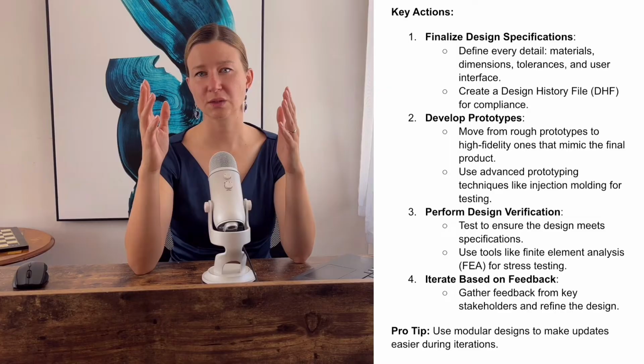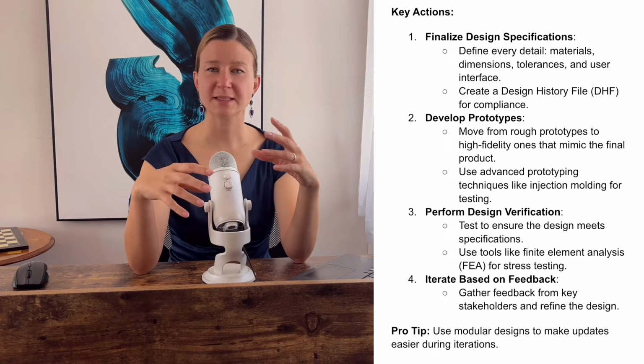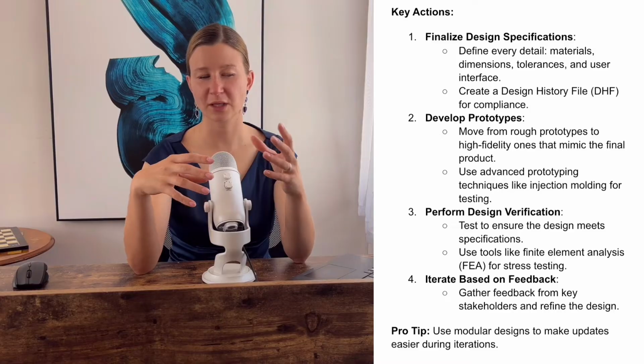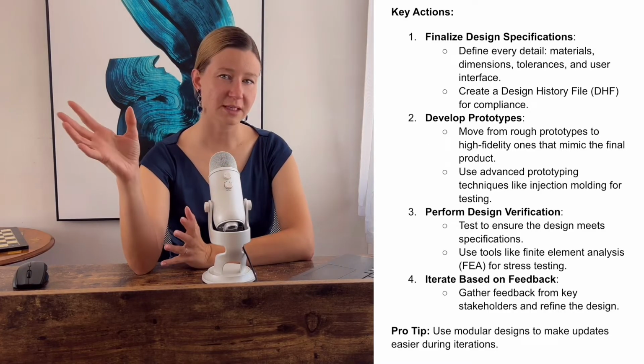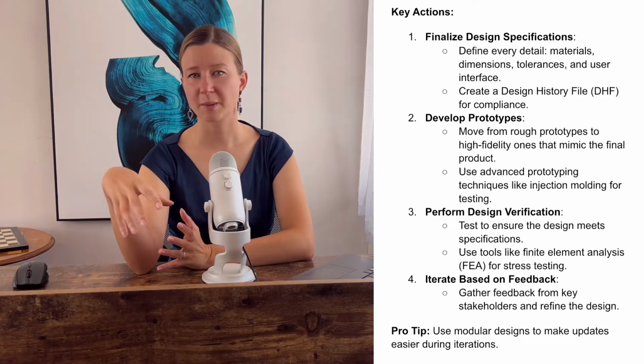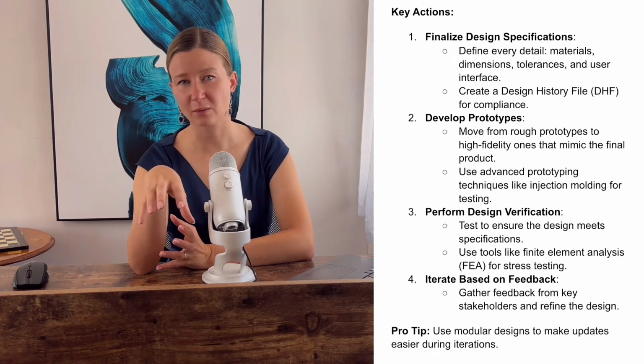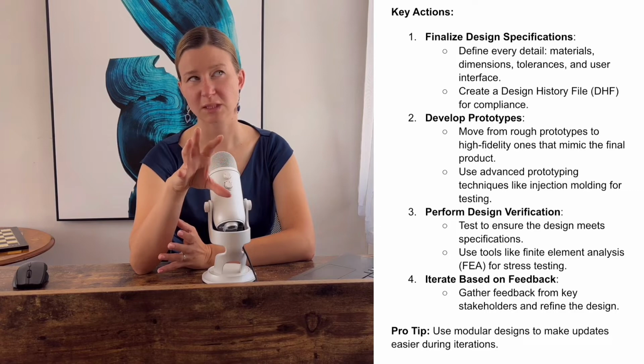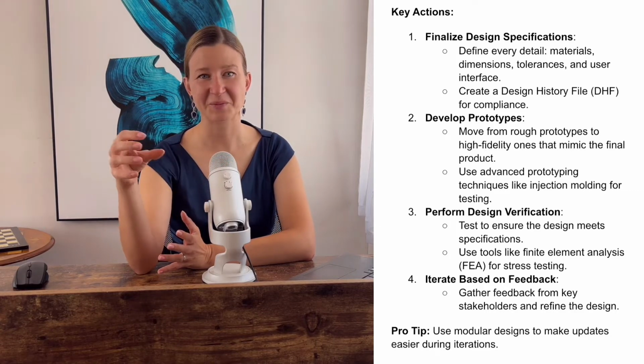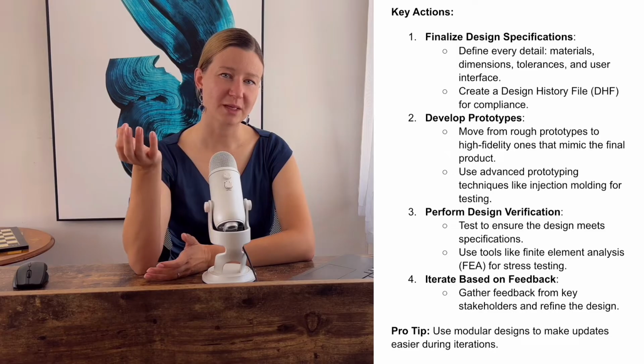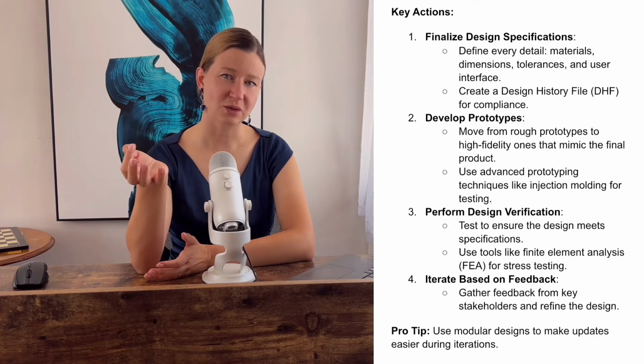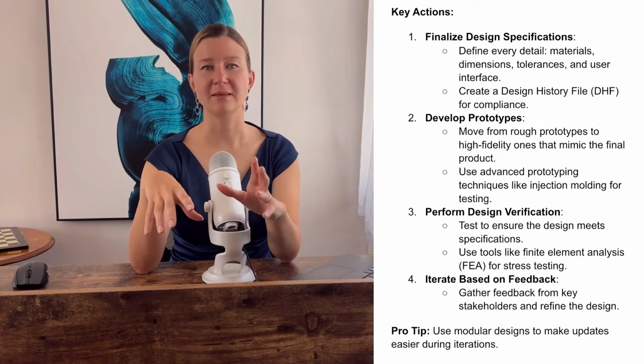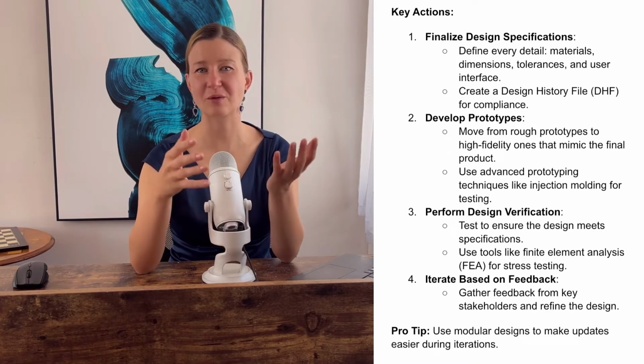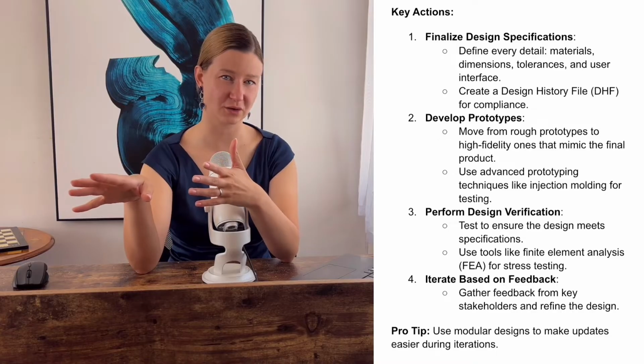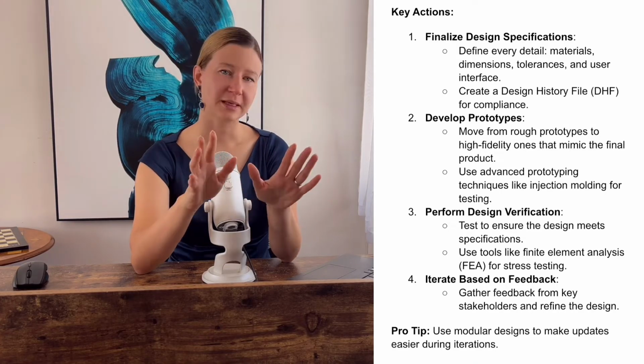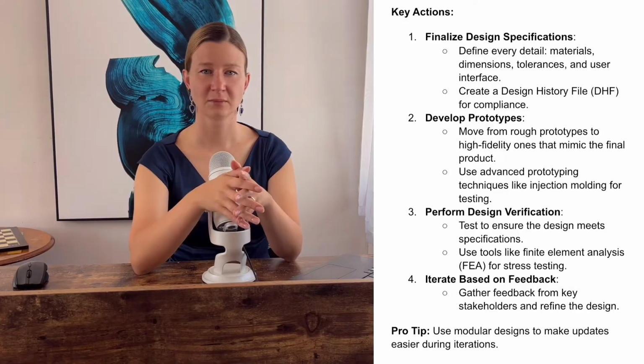Here is a tip: use modular designs where you can. That means that parts of your device can be changed or updated without having to redesign the entire thing. For example, if you need to improve one component, you can swap it out without starting over, because this approach typically saves a lot of time and money later on. This stage of design and engineering is all about being precise and improving as you go. The more work and, again, the more documentation you do here, the fewer problems you'll face when it's time to manufacture your device. So, no rush. Take your time. Test everything. Keep refining your design.